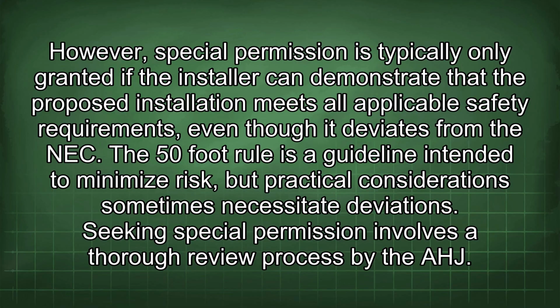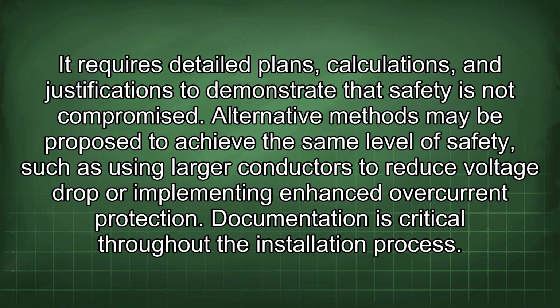The 50-foot rule is a guideline intended to minimize risk, but practical considerations sometimes necessitate deviations. Seeking special permission involves a thorough review process by the AHJ. It requires detailed plans, calculations, and justifications to demonstrate that safety is not compromised. Alternative methods may be proposed to achieve the same level of safety, such as using larger conductors to reduce voltage drop or implementing enhanced overcurrent protection.